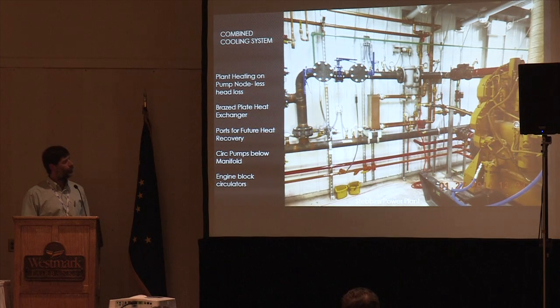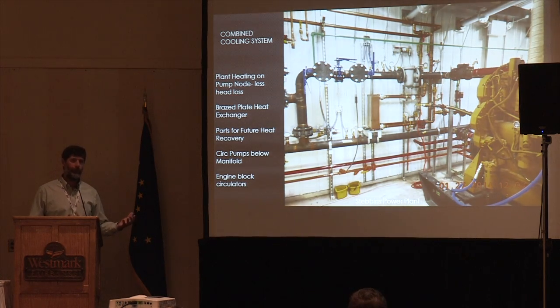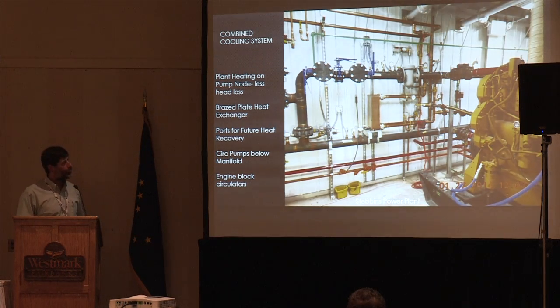So you want big pipes, you want to have minimal valving. We used to also put large shell and tube heat exchangers in our cooling systems where the full flow of the coolant would have to go through that heat exchanger, which creates a lot more restriction.